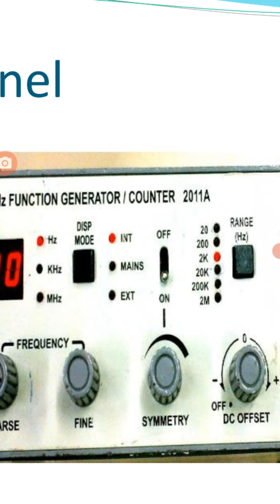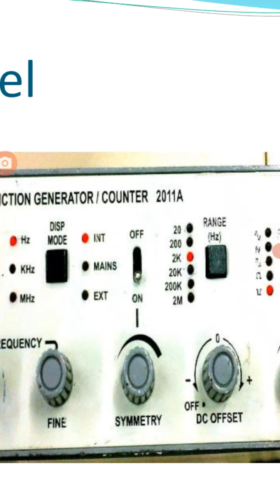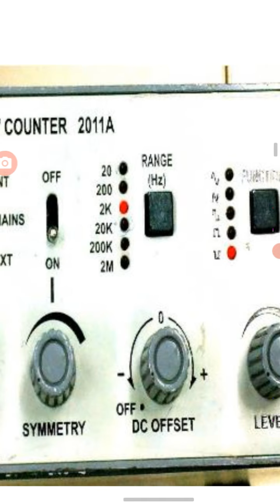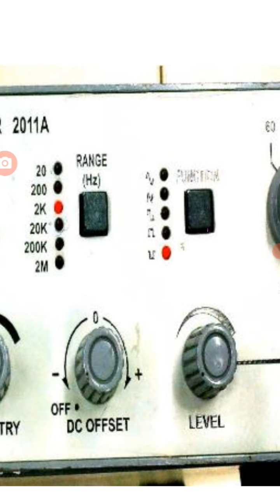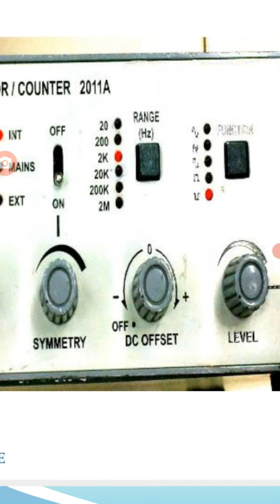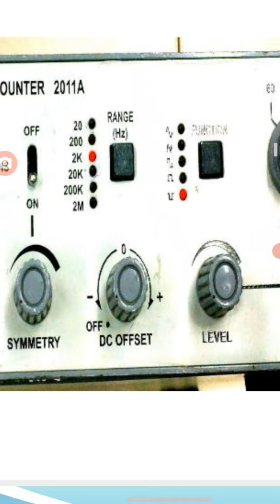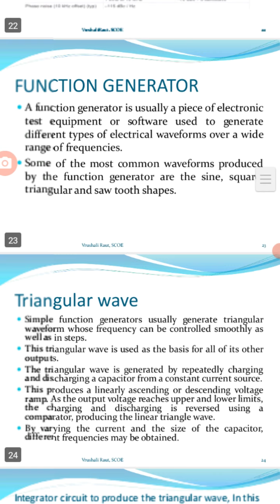There is a frequency range of hertz, kilohertz, megahertz. Then frequency, coarse, fine. Fine is for low frequency generation. Then internal, mains or external is there, on-off is there. Then which range we want to generate: 20 Hertz, 20 kilohertz, 200 kilohertz, 2 megahertz and so on. This is a range selection switch. That means we can generate a variety of ranges. Then there is the symmetry of the square wave or sine wave. The positive peak must be symmetric to the negative peak, and in the square wave the same should be there. Then DC offset and level are also there, output, attenuation and other things are also there.